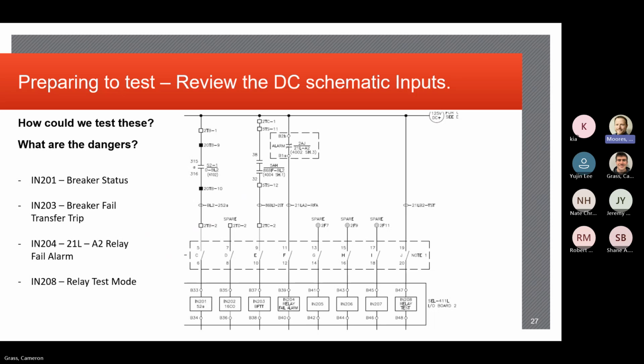So there's a lot of stuff. It could be alarms. Inputs could drive display points. They could drive LEDs. Maybe they're only used in an SER, right? But all of those things have to be tested and documented. Because at the end of the day, what are we trying to accomplish? We're making sure that this relay, when it needs to, sends an abnormal condition or some sort of control, it does what it's supposed to when it needs to, and it doesn't do anything when it's not supposed to.